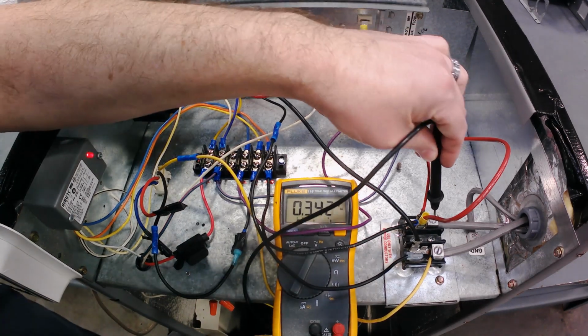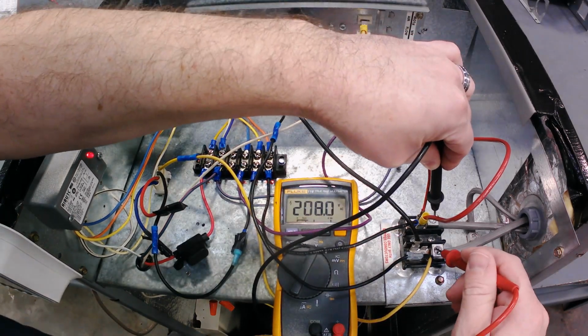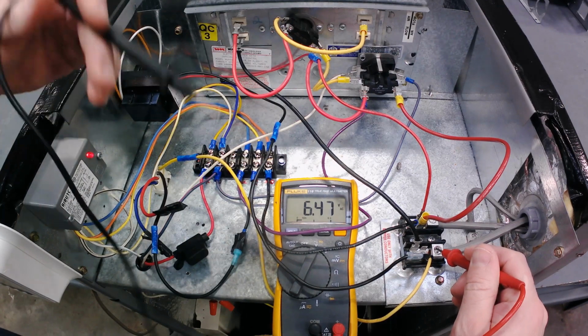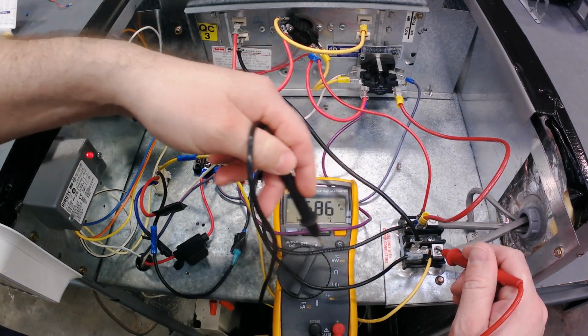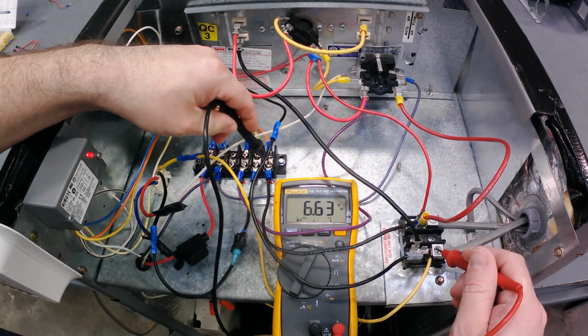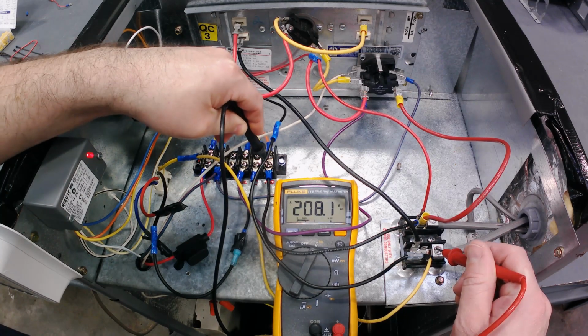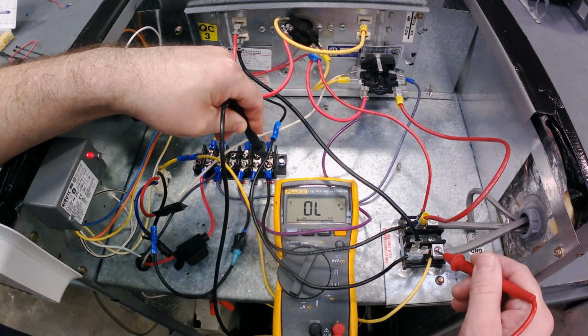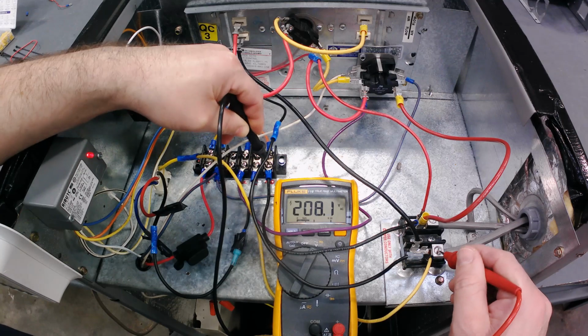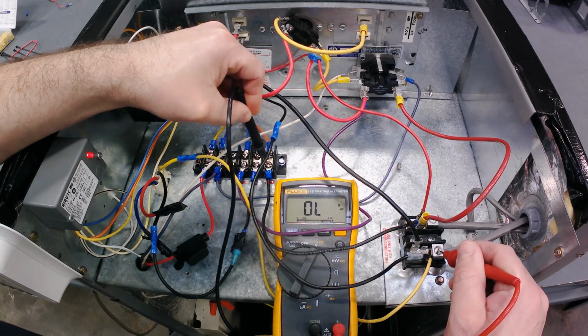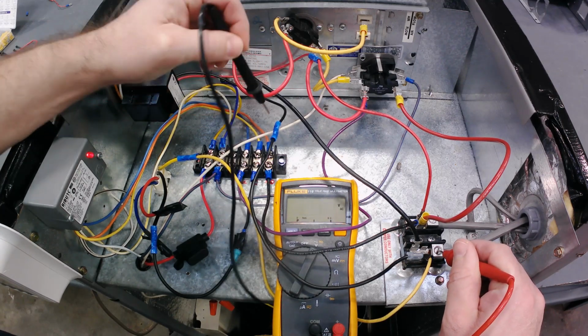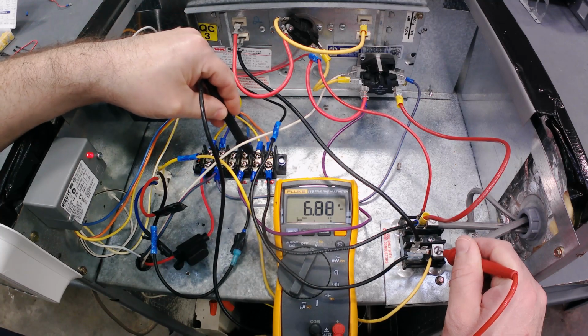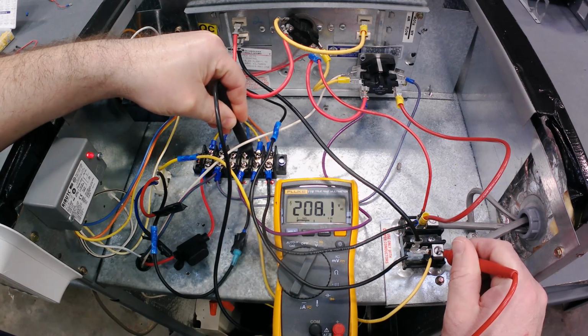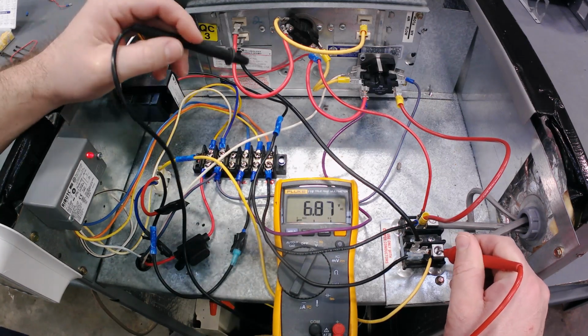All right, so this is L1 and this is L2. So I've only got the fan on, so if I was following, I would follow this going into the normally open. So I've got my L2 over here on this bottom terminal screw of the terminal block. So that's power going in. If the switch is closed, then it'll come out here on the common. So I know that my fan should be running, and of course it is.